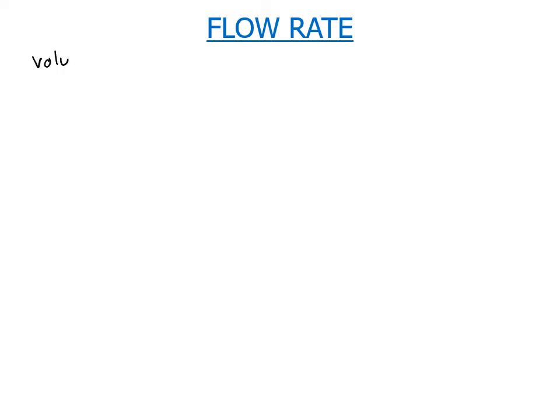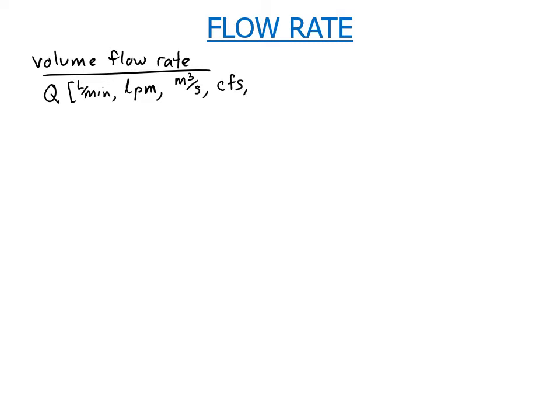We'll talk about two different types of flow rates. The first is the volume flow rate, and I'll use the variable Q to refer to that. It can be in units of things like liters per minute (LPM), cubic meters per second, CFS (cubic feet per second), SCFM (standard cubic feet per minute), or ACFM (actual cubic feet per minute). This depends on whether we're reporting the volume under actual conditions or converting to standard conditions — standard temperature and pressure.